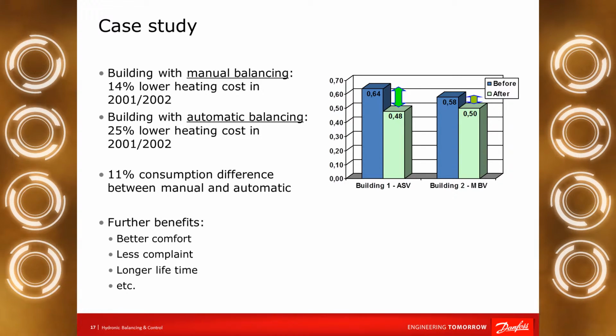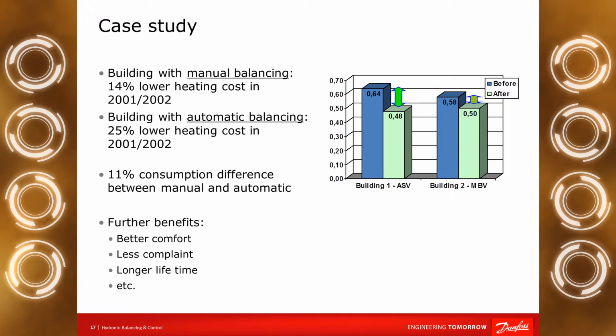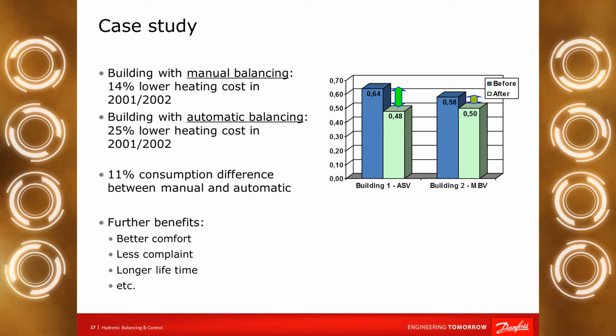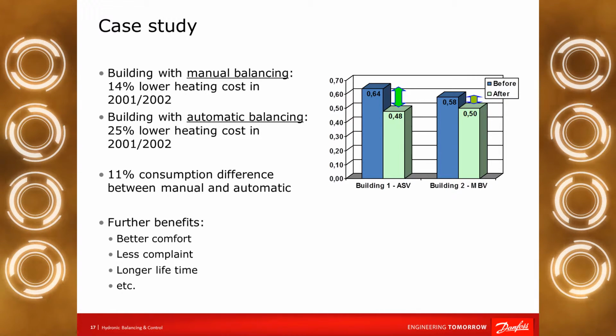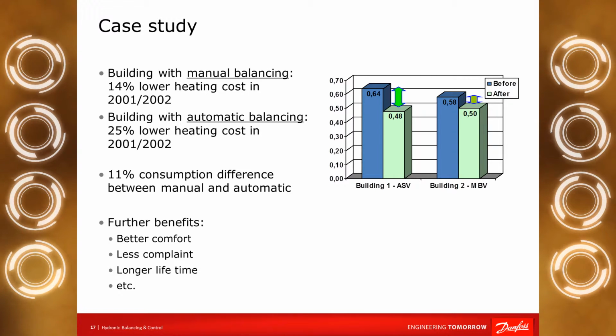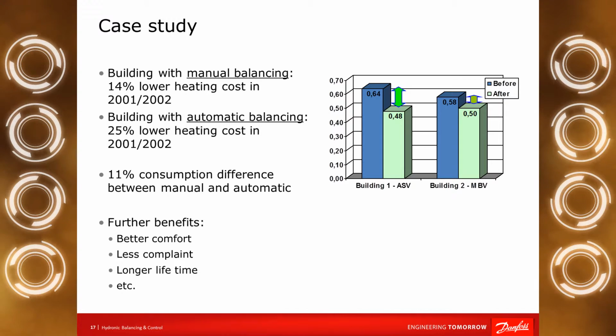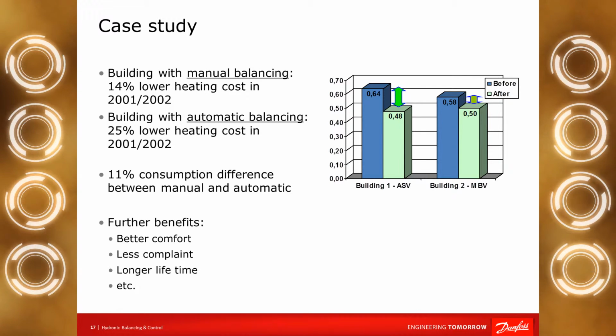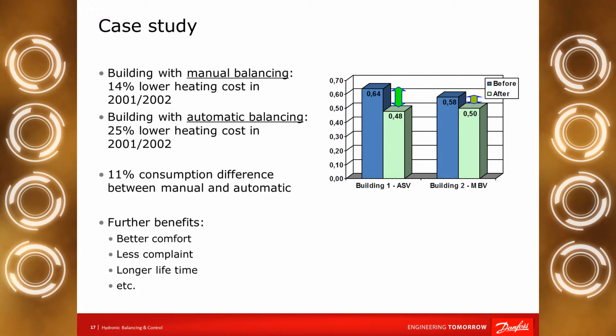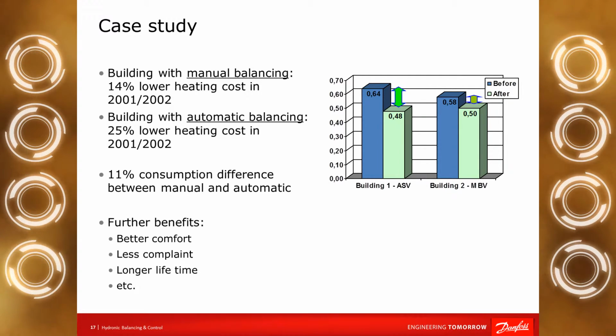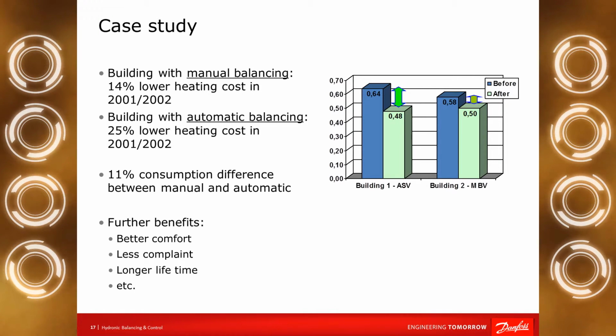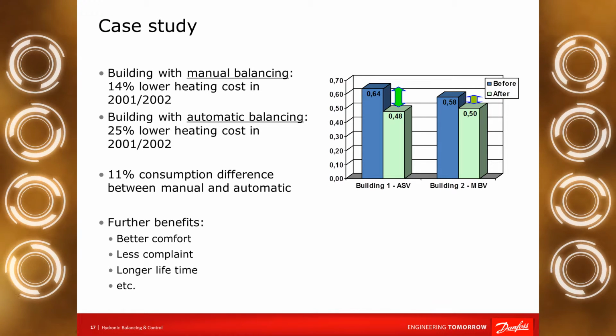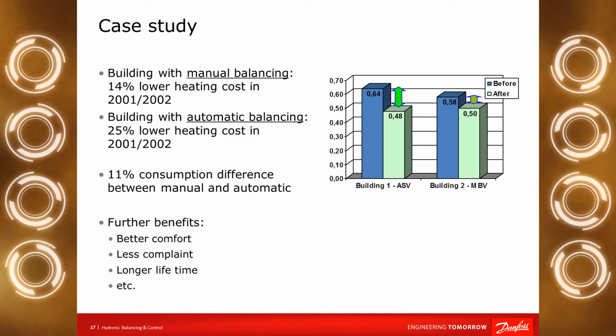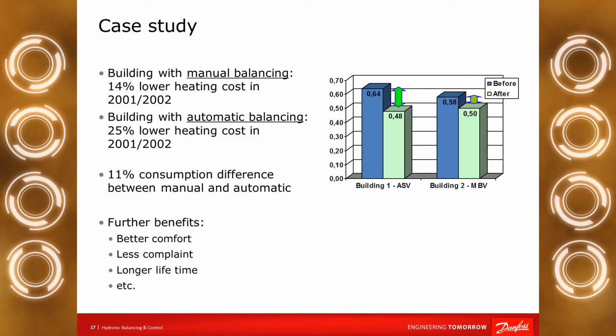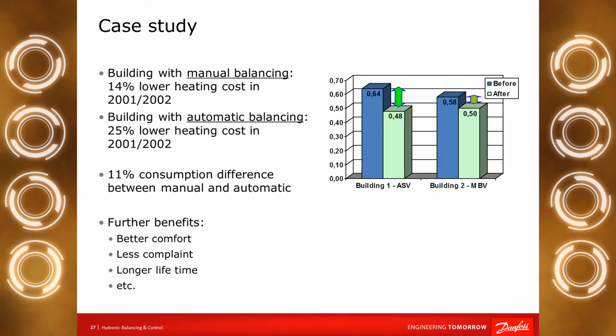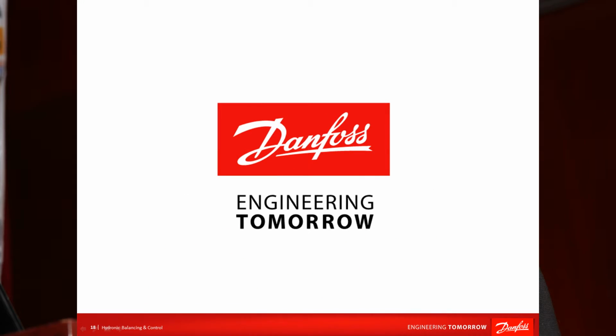So how can we help on the secondary side to improve the efficiency of the district heating system? Please use automatic balancing for the 2-pipe radiator heating system. There are a few further benefits if you use this solution. Not only the energy saving, we can also ensure better comfort for the users, fewer complaints to the maintenance people, and a longer lifetime over the whole working period of the system. And of course, there are some others like environment friendliness and so on, but because of lack of time, I wouldn't like to talk about these additional savings.